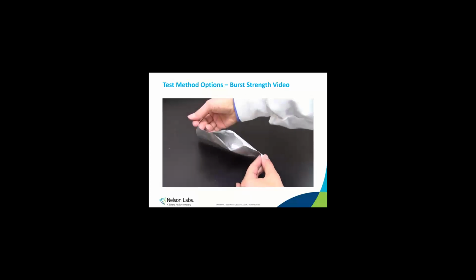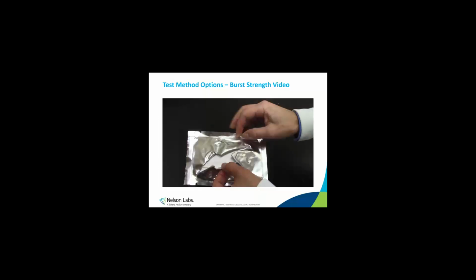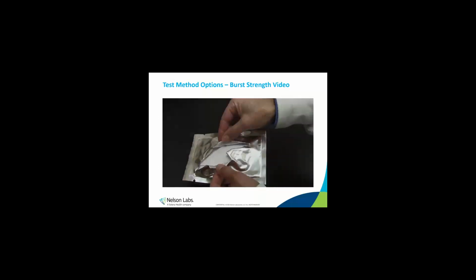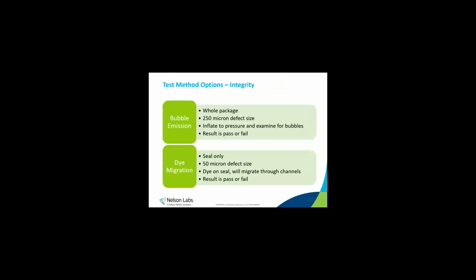Now, sometimes if you have a seal that's not designed to be peeled open, you may end up with a package failure, which again, neither of these are bad. That's just showing the package doing what it was intended and designed to do. Now let's look at some integrity options. Integrity tests are intended to make sure that there's no breaches to the sterile barrier that could render the package non-sterile. Here, the most popular options are bubble and dye.